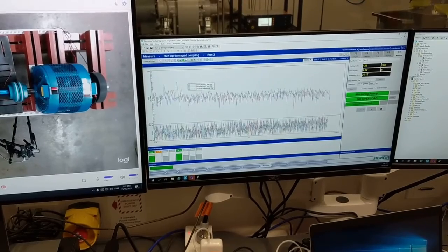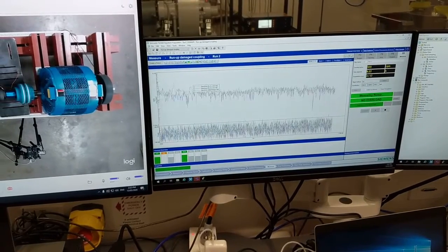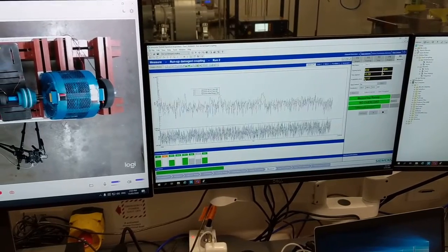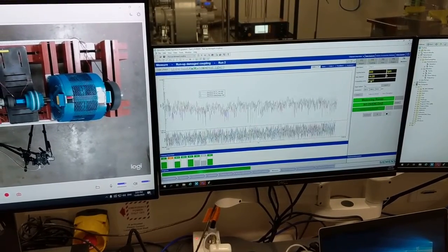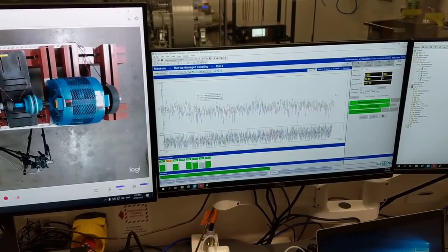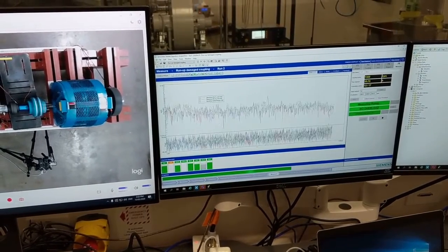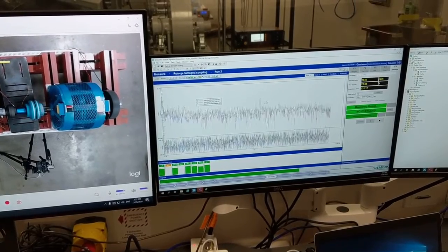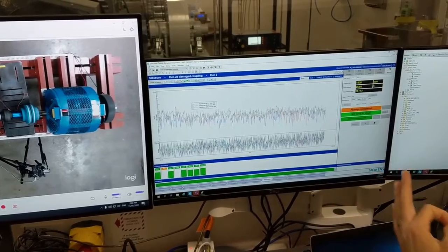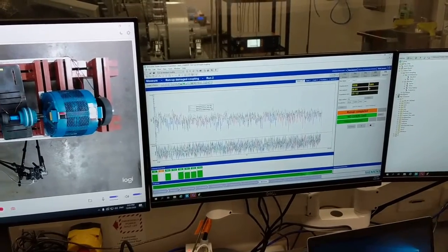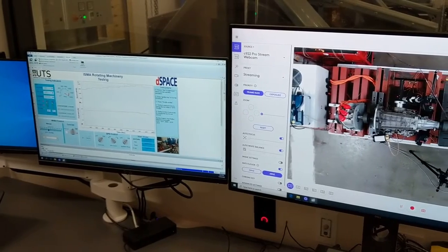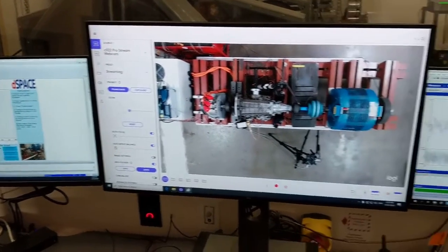Here you can see the RPM gradually increasing, and the acquisitions as we cut through this 100 RPM increments, 6 acquisitions, 7, 8. So these are individual FFTs at different RPMs, and we'll ultimately generate a waterfall. Here you can see this peak slowly progressing through the spectrum, and when we hit a resonance it gets slightly higher, and then it drops down again. That's the end of the run-up now. So we have 17 FFTs. Paul will slowly drop the speed down on the machine.